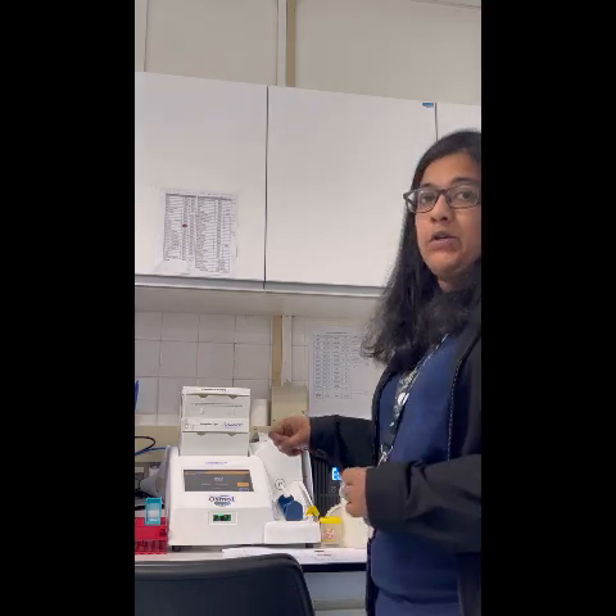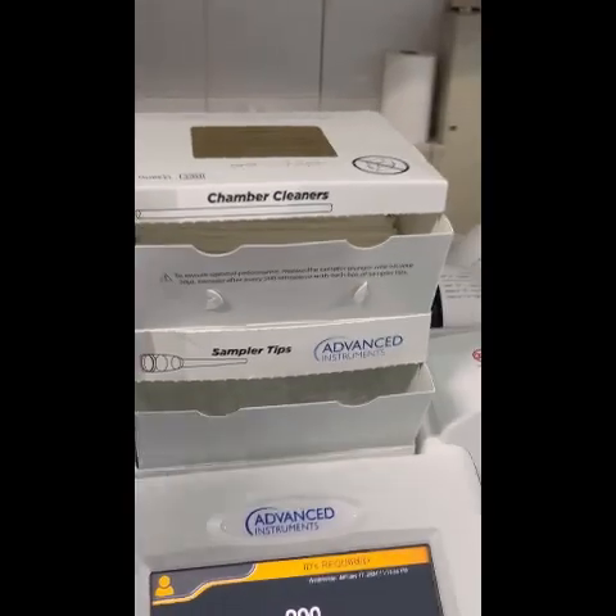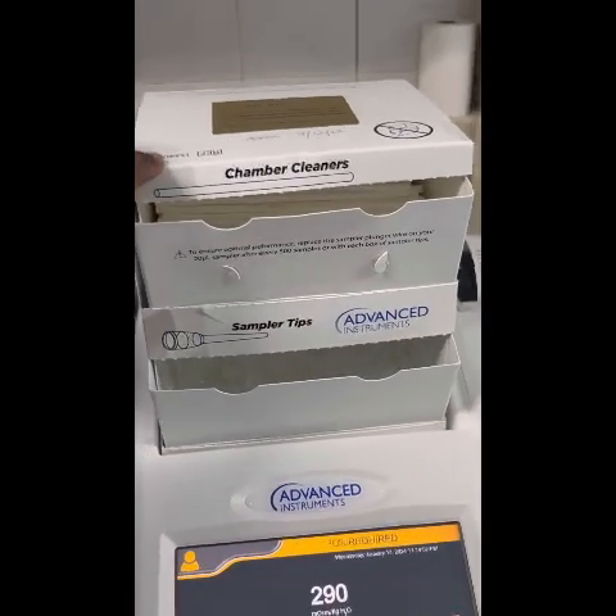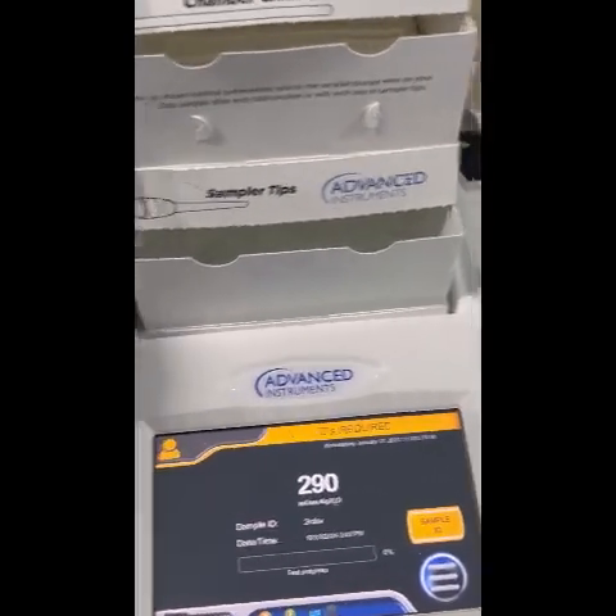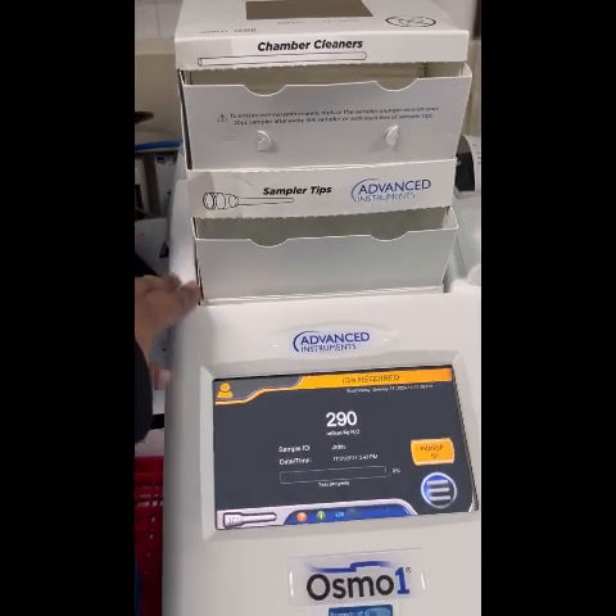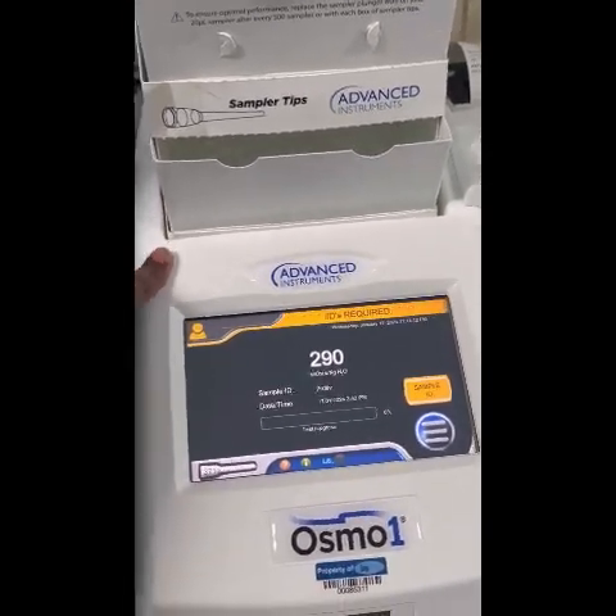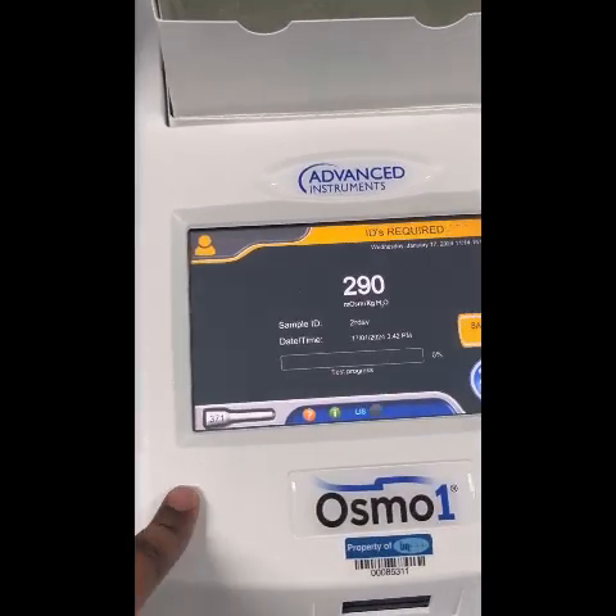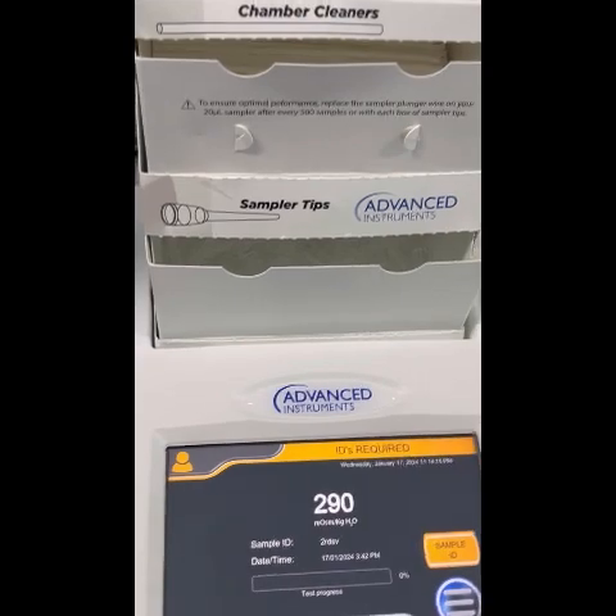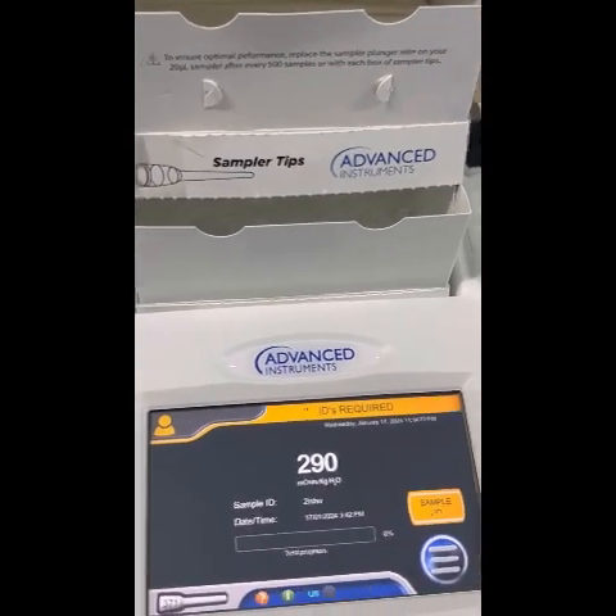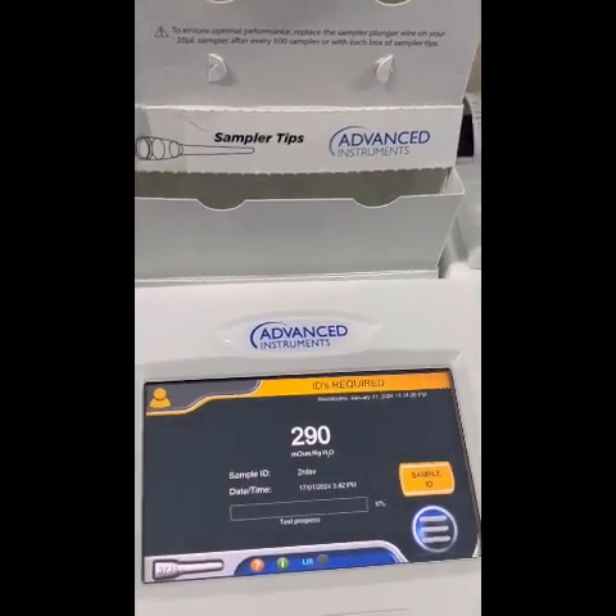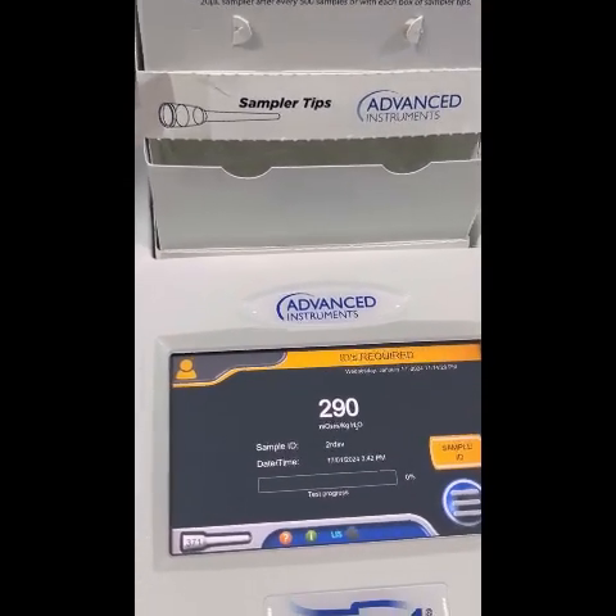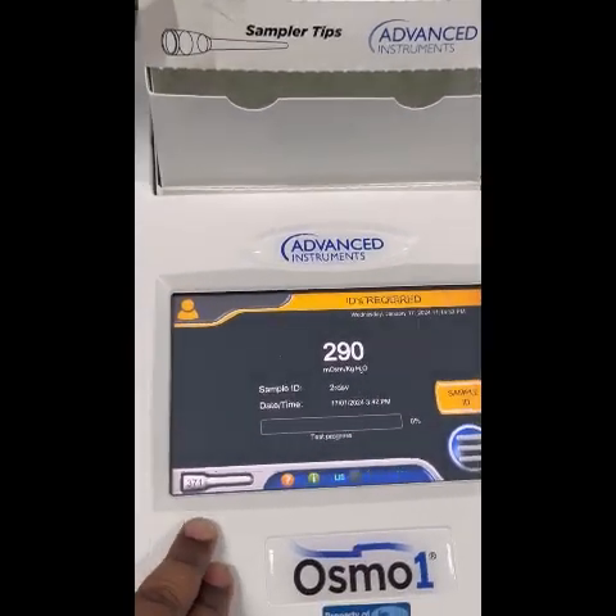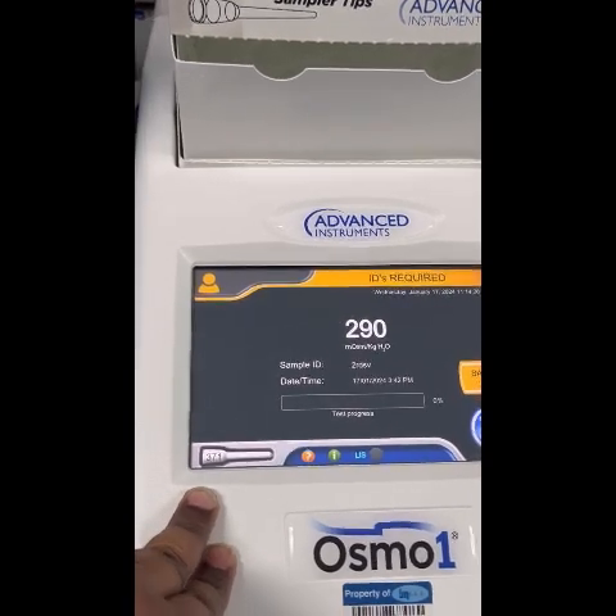Let me show you the parts of the osmometer. So we start with the top here. This is the chamber cleaners, and these chamber cleaners are actually attached to the osmometer. There is an RFID at the bottom here. This RFID counts the number of chamber cleaners and sampler tips that are on top here, and every time we use one, the number reduces. So every time we open a chamber cleaner and sample tips, we have 500, and once the 500 finish, it will alert us and we have to change to a new one.